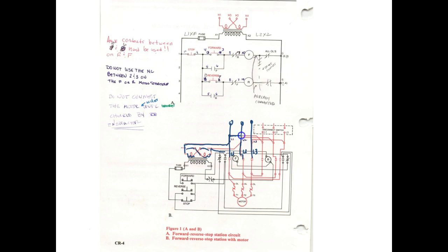Then I'm going to take L2 and come over here. Oh, they put their disconnect there. Then I'm going to come down to L1 on the other motor starter. Then I'm going to jump over to L2 of the second motor starter. And then I'm going to jump L3 over to L3 on the motor starter.